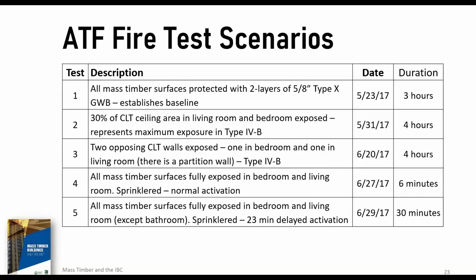Test number 3 is 2 opposing CLT walls, and we'll show you in the schematic where those walls were, one in the bedroom, one in the living room, again to simulate actual field conditions to be installed in type 4B construction. Test number 4 is all mass timber surfaces fully stripped of protective gypsum wallboard at a normal activation of the sprinkler system. And you can see the corresponding time there. And test number 5 is, again, all mass timber surfaces exposed and a planned 20-minute delay that they stretched out to 23 minutes before a simulated charging of the sprinkler standpipe. And you can see the corresponding time duration there.